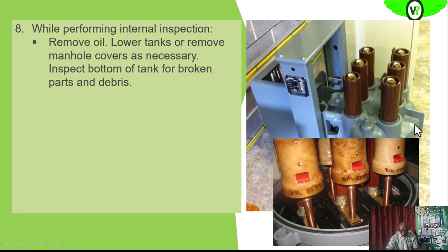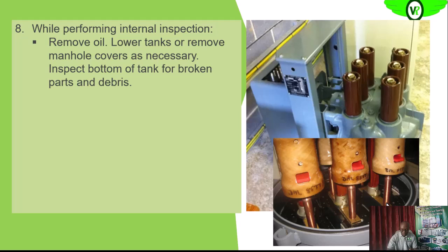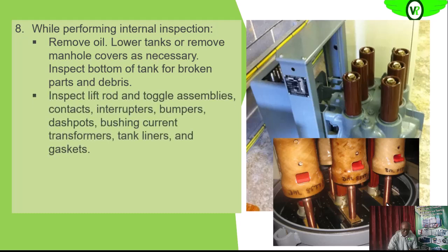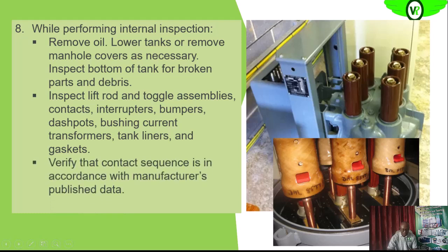Once it is open like this, we also want to check the contacts for signs of discoloration and signs of stress on them, and check the alignment to see that the movable part and the stationary part are properly aligned, so that during closing and opening of the circuit breaker there won't be stress on those contact points. We also want to check the interrupters, bushings, liners, and gaskets or seals to see that they are okay.